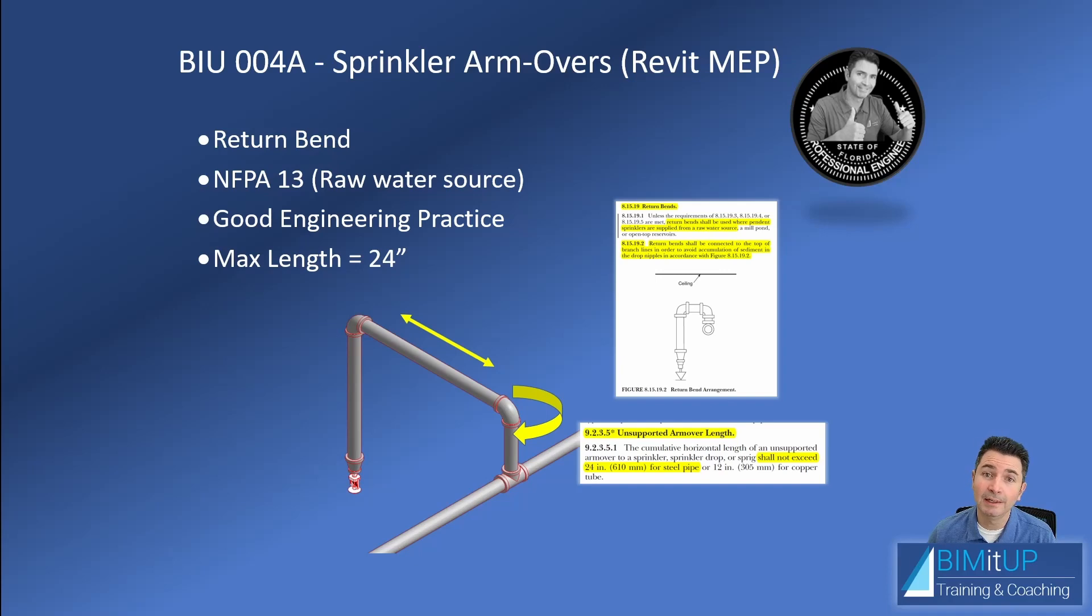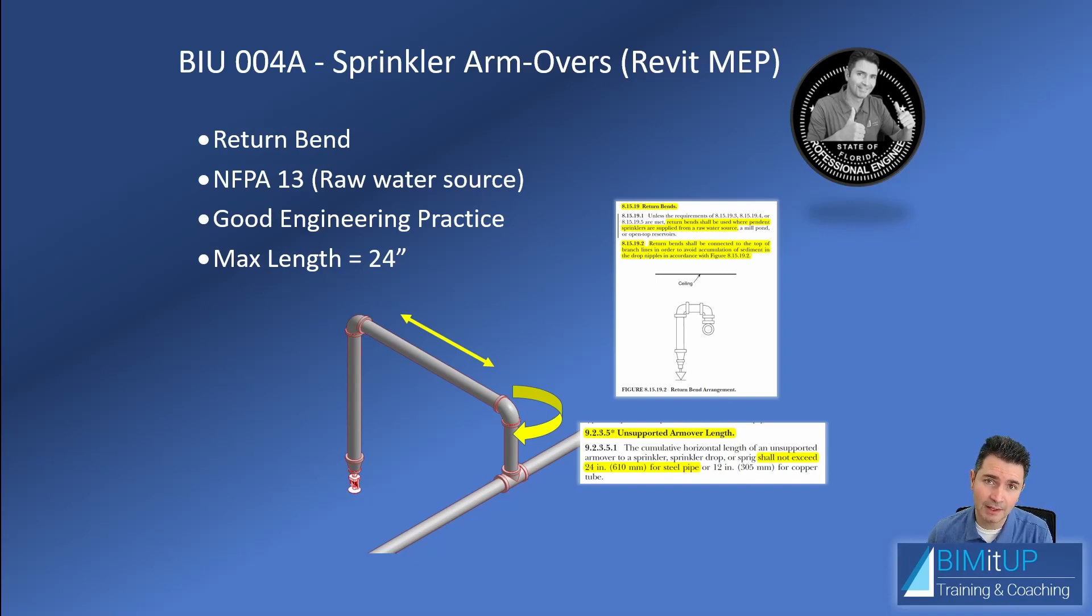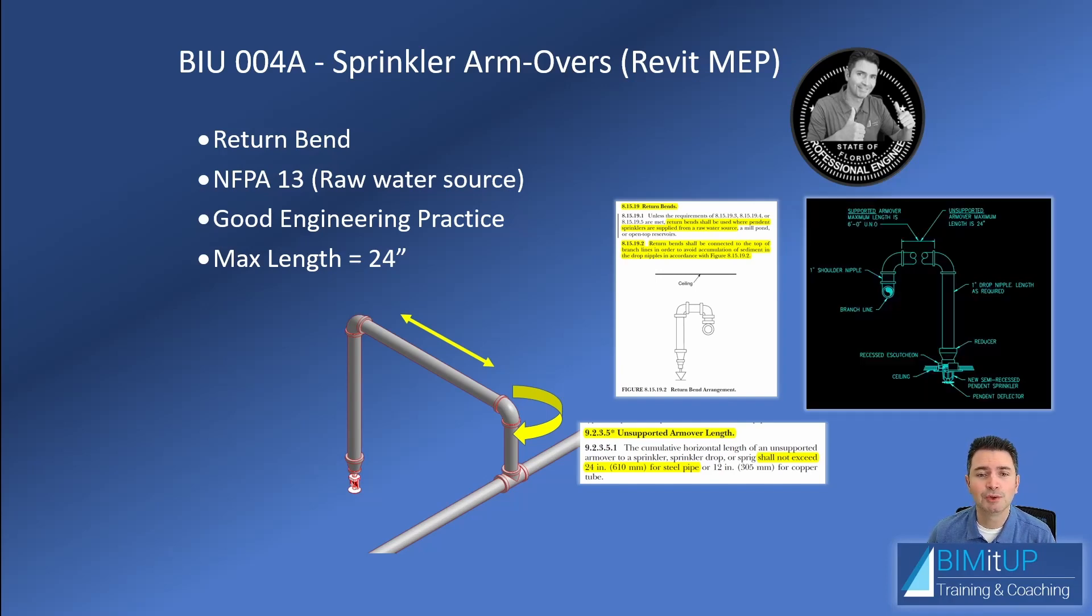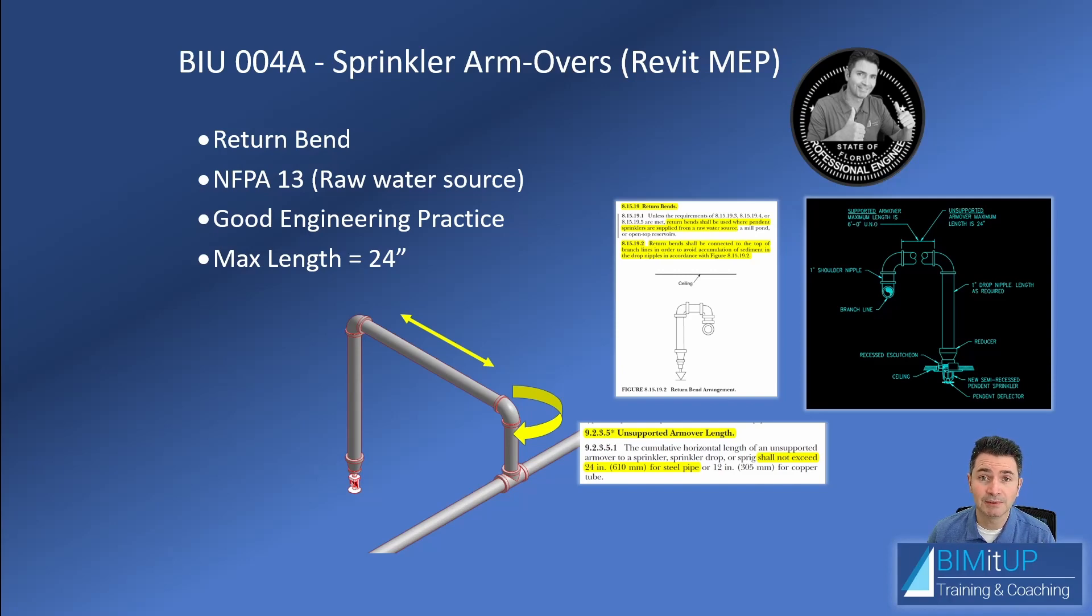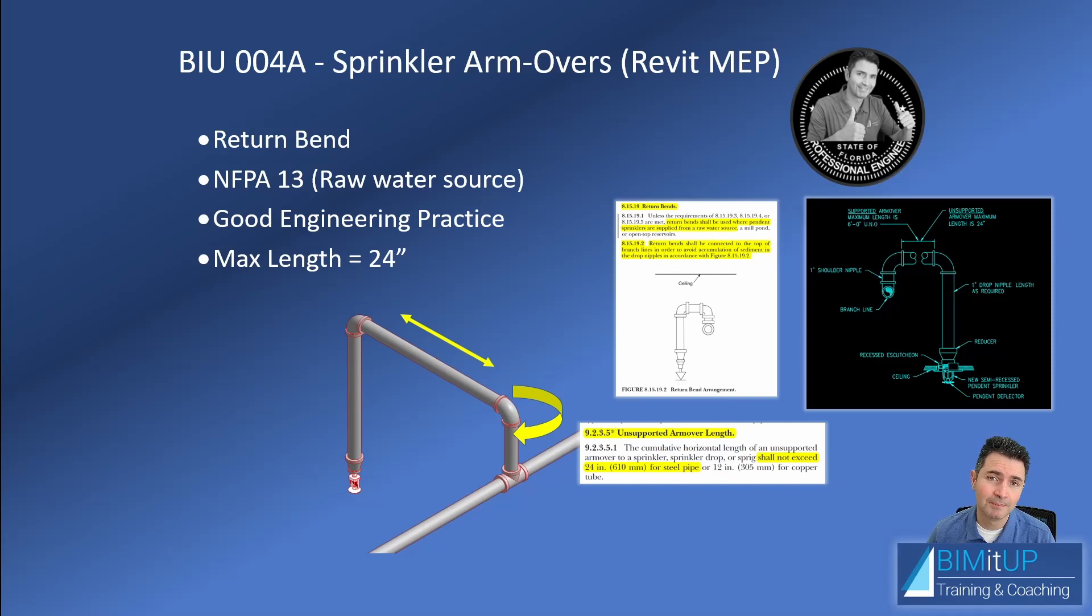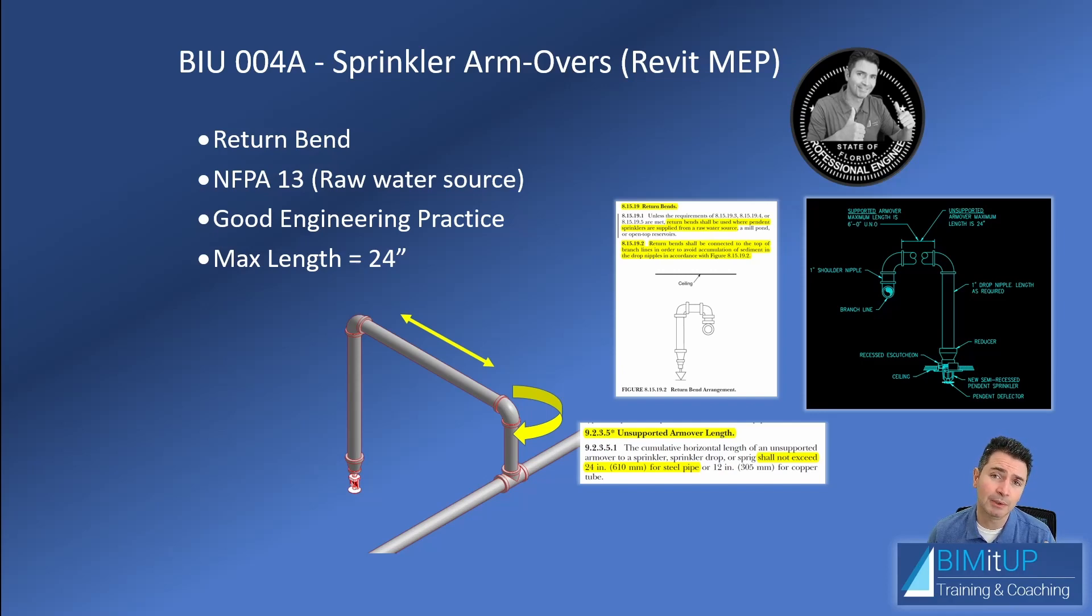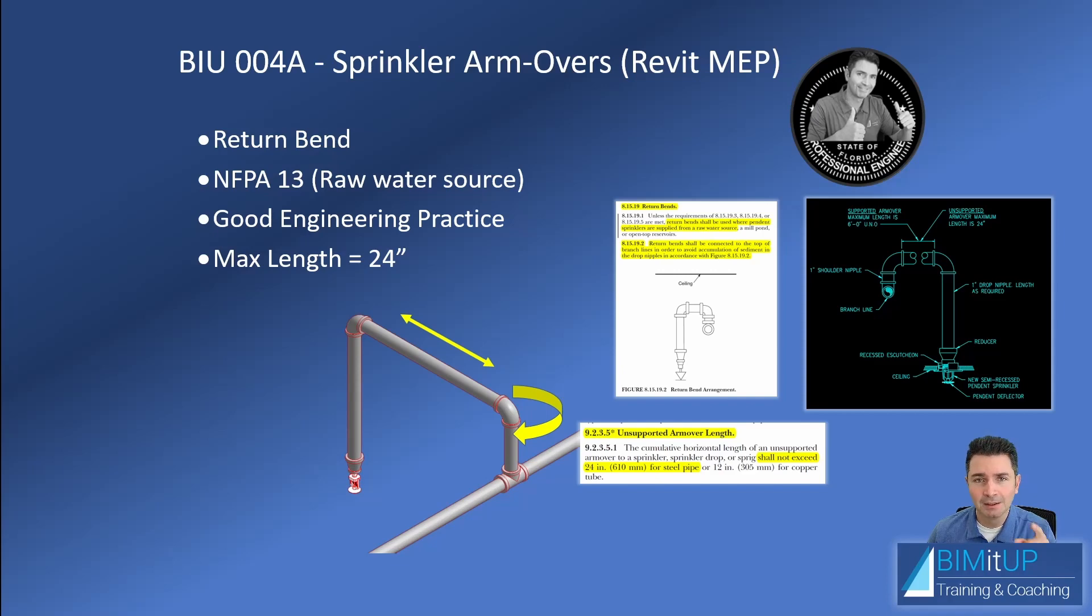A couple of pro tips: the maximum unsupported length of that horizontal piece is 24 inches. And you should always include a detail in your drawings to specify both the maximum unsupported length and your preferred maximum supported length, typically keep it at four feet and some people allow six feet. So let's do it in Revit.